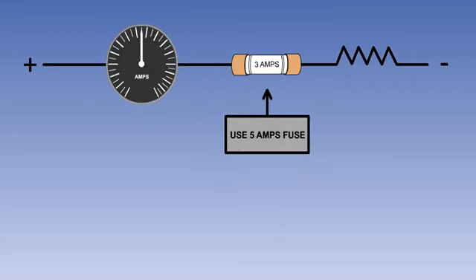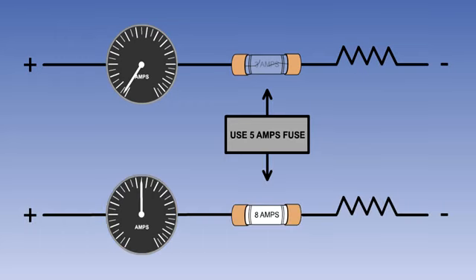It is important always to replace a fuse with one of the correct rating. Using a replacement fuse of a lower rating will cause it to blow prematurely, while using one with a higher rating will leave the circuit vulnerable to excessive current and the subsequent risk of overheating.